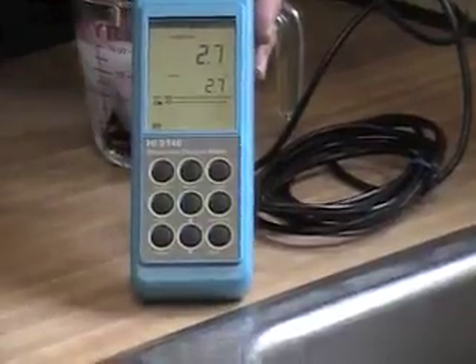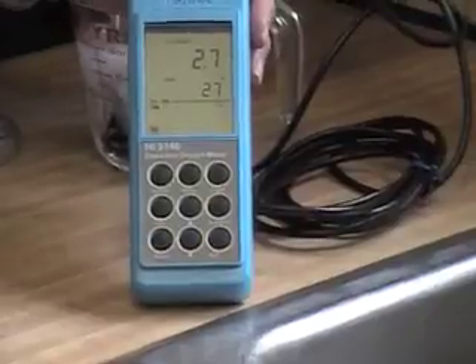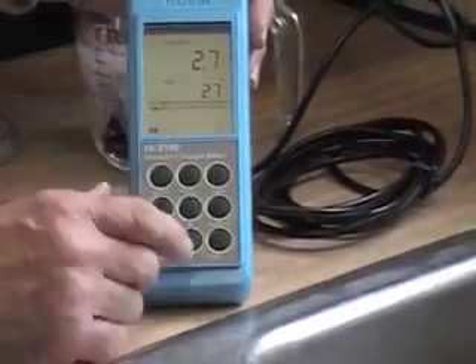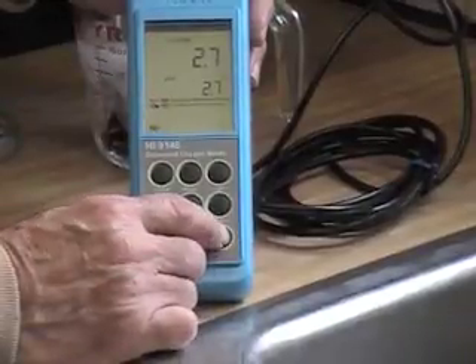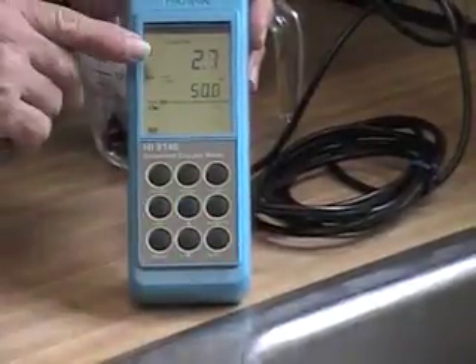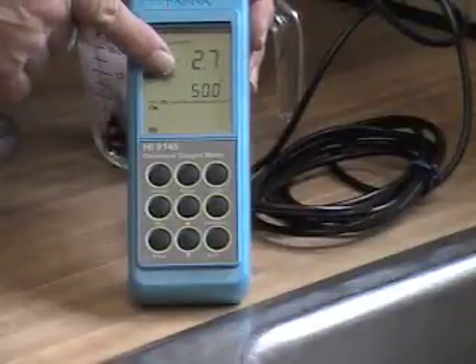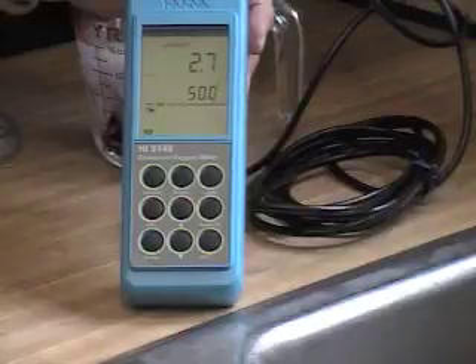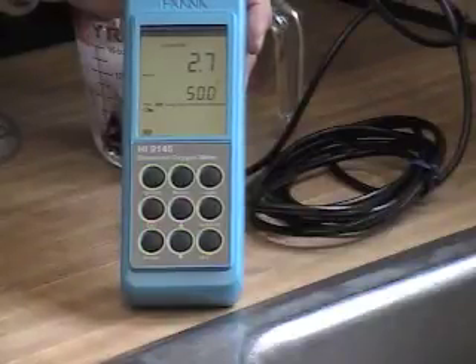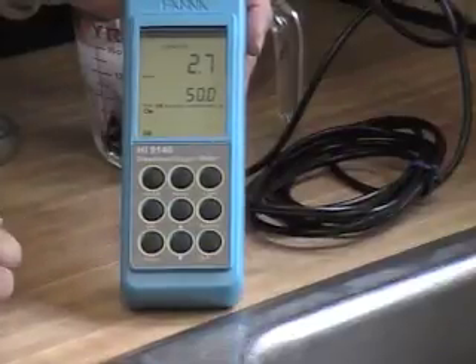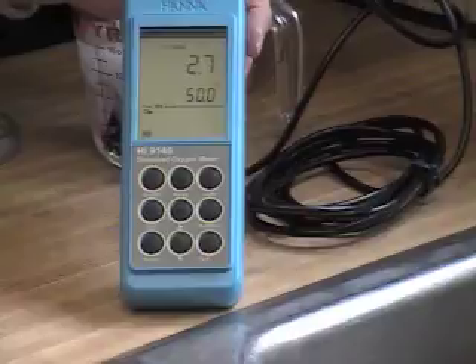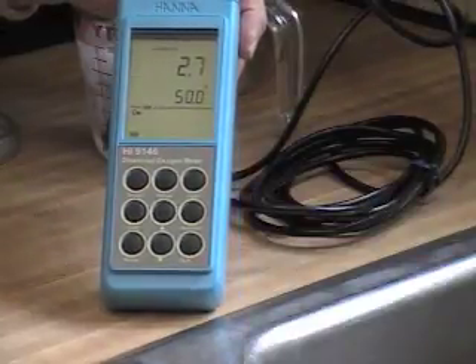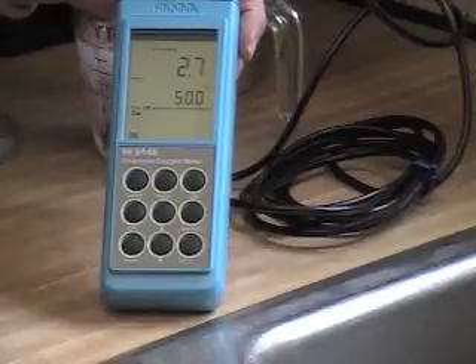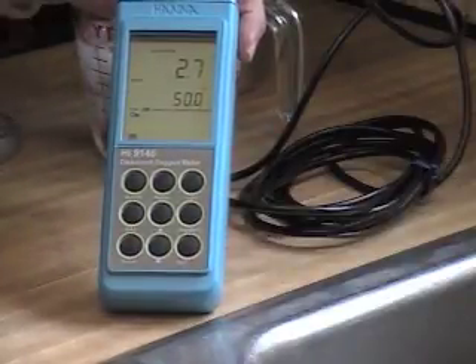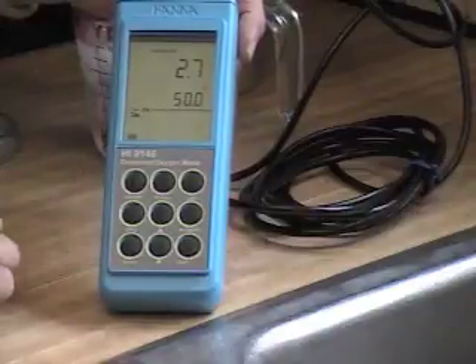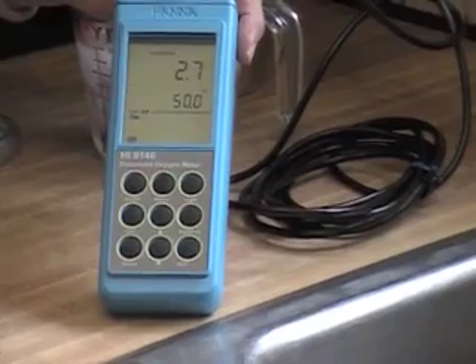I checked with my magnifying glass, read my thermometer. It's 2.7 degrees water temperature. Once those two agree, it's flashing down here for me to confirm. So I'll hit the confirm button, and you saw immediately we went from the 2.7 that I had down there to 50 degrees, and now it wants me to place the probe into the 50 degree temperature. If you remember, I preheated some water and put it in this thermos. The water temperature in this thermos is way above 50 degrees, but I only half filled it, and now I use some of this cold water to kind of ease down to the 50 degree temperature. So I'm going to proceed to that step.